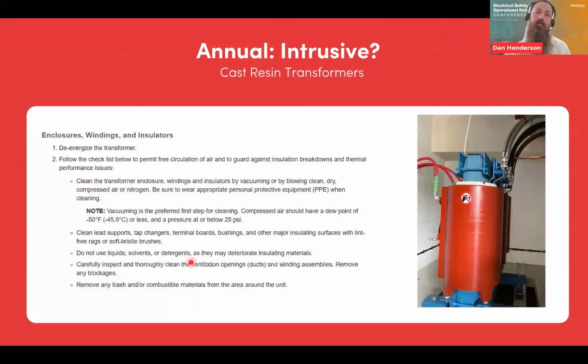And then finally, possibly a point of contention, but a lot of people lean towards dry type transformers, so cast resin transformers on the networks, because they're normally less expensive than oil filled. There's obviously, from a loss prevention and risk management perspective, insurance prefer that because you haven't got a fire risk with oil. Even if you use synthetic, it's still got a flash point at a certain point. There's less working parts. The maintenance, there's supposed to be maintenance free, a lot of these. But typically, if you're going to follow the power transformer element within NFPA 70B, this would kind of fall in line with a 5-yearly item.